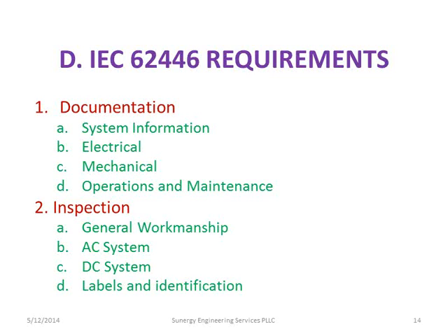And they require a very detailed operations and maintenance plan. Basically, the owner needs to know how to turn the system on. They need to know what it means if the system's working right, how they know, and if it's not working right, they need to know that, and they need to know how to do an emergency shutdown at a very minimum. And even a residential system should give their owners that bit of information. You know, if you see this, call me. If you see this, here you go, turn it off here, make sure everything's safe, and then call me, right? That sort of thing. And then the inspection is just an overall inspection to make sure that everything's matching the documentation and everything's been done properly, that there's good workmanship, and that everything has been done the way it's supposed to be done. And this is all before you even go to the point of starting the testing.